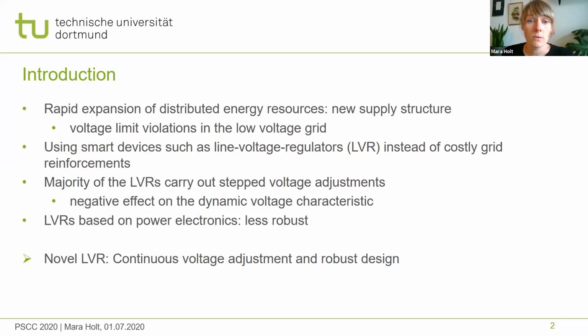To solve this issue without costly grid reinforcements, one approach is the use of smart devices such as line voltage regulators. However, the majority of these devices carry out stepped voltage adjustments, which negatively affect the dynamic voltage characteristic. In addition, line voltage regulators based on power electronics are less robust due to a relatively high failure rate. For this reason, I want to present another line voltage regulator, which can merge continuous voltage adjustment with a robust design.